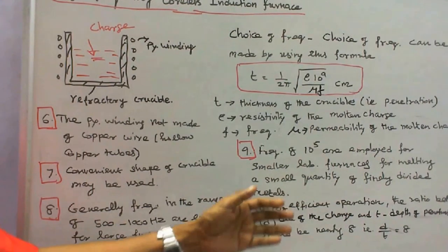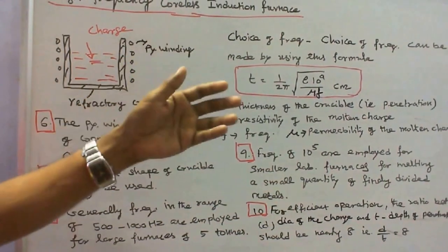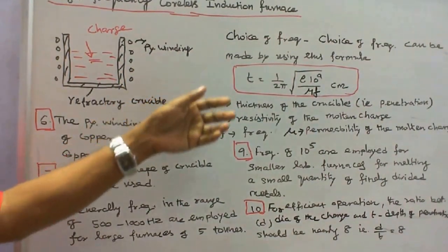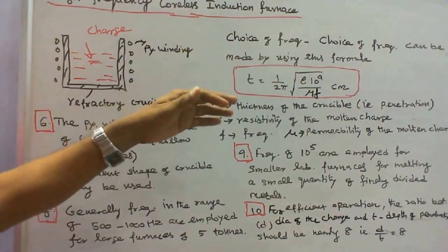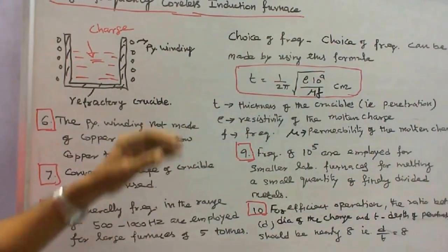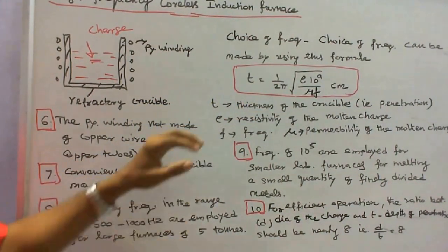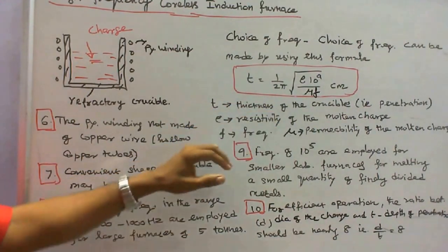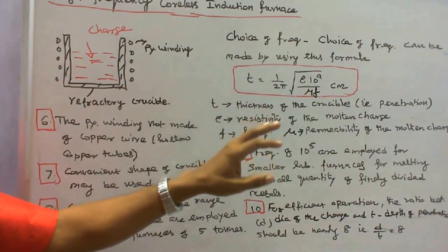That is, D/T = 8. The choice of frequency can be made by using the formula: T = (1 / 2π) × √(ρ × 10 to the 9 / μ × F) in centimetres, where T is the thickness of penetration, ρ is the resistivity of the molten charge, F is the supply frequency, and μ is the permeability of the molten charge.